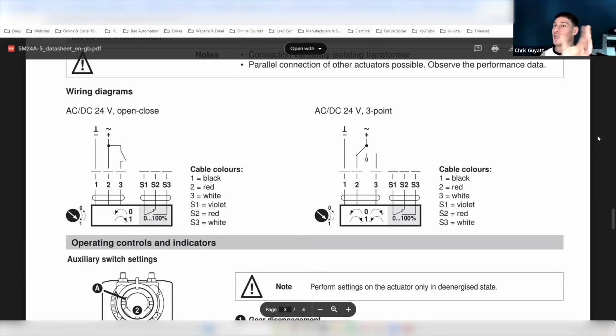So it's basically, it tells us the state of something. Just going back to the hot water system, it tells us, when we send power to that valve to open, and then when that valve is fully open, the auxiliary contact then sends, or can send, a signal to something else to tell us the status of that valve is fully open, which we can then use to bring on the pump, because we don't want the pump to come on before the valve is fully open. We don't want a pump to burn out running against a valve that's closed.